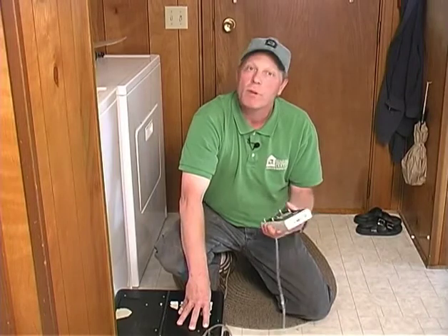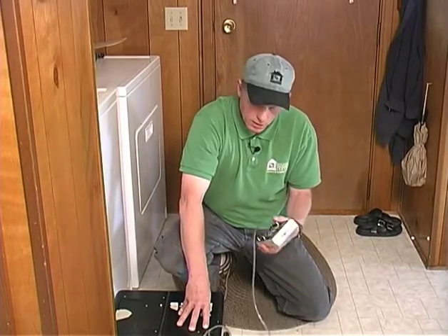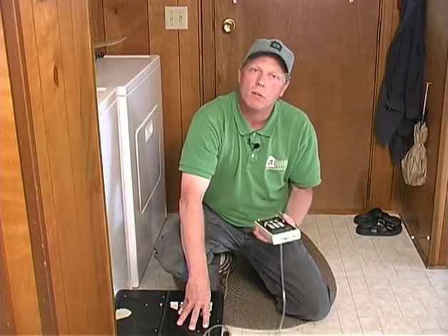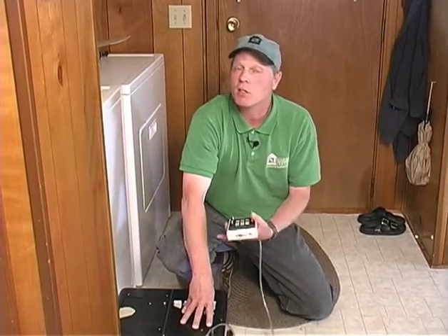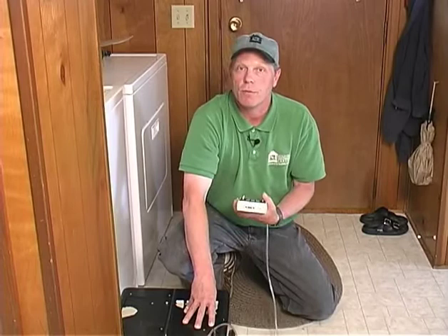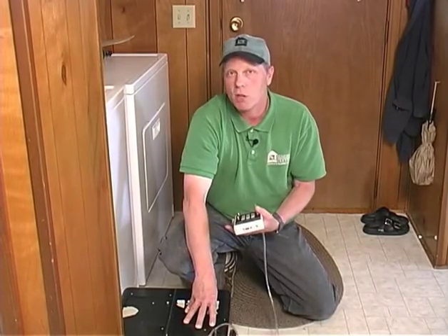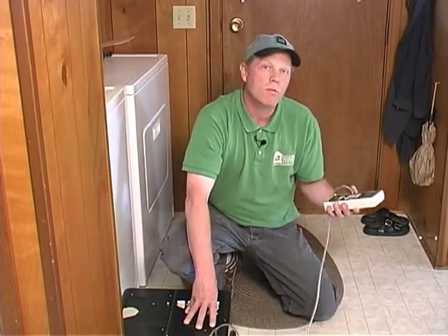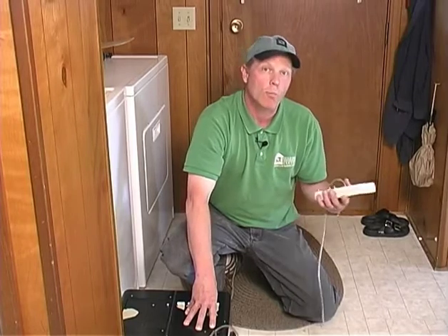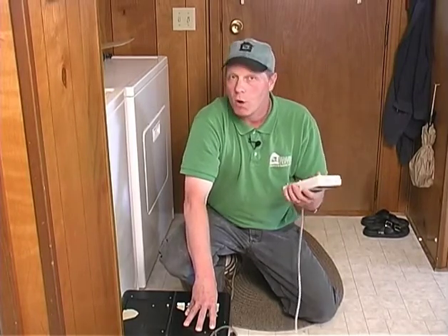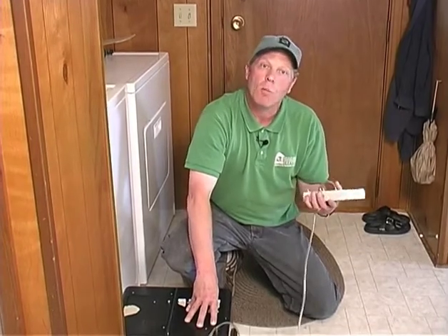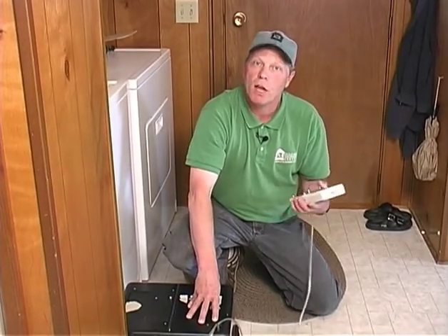If it's above, we might need to do some work. Essentially, what this is reading is, if the number is higher than 1, there's a suspected leakage site near this register. I'm going to go ahead and take this pressure pan now and do the rest of the duct registers in the home. And I will write those down on a little map of the home, and that will tell me essentially where the leakage sites are in the duct system.